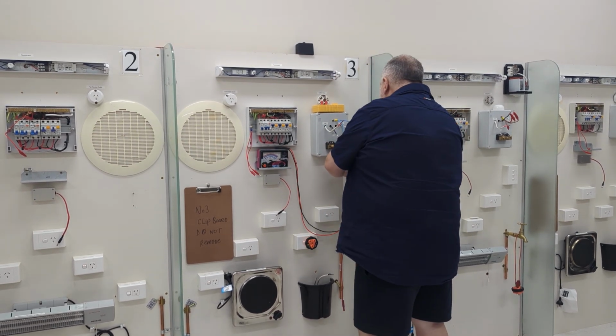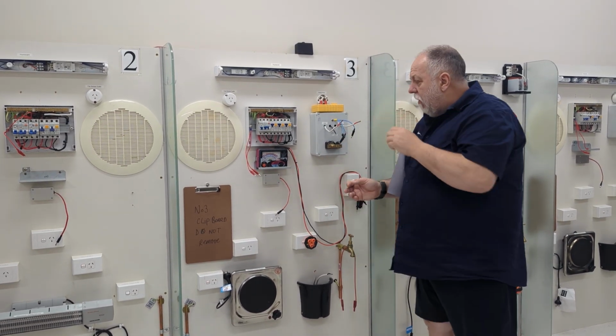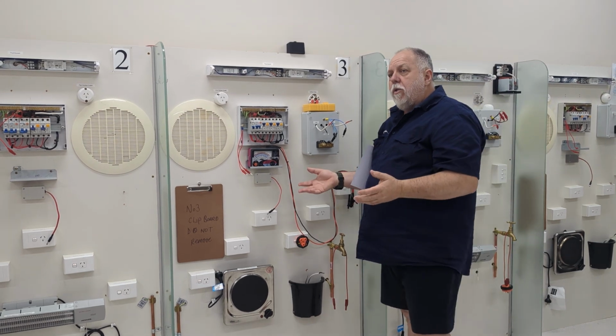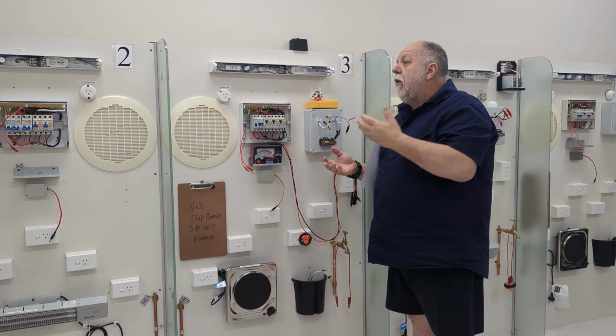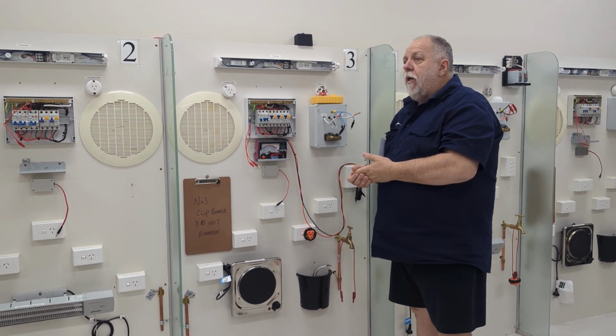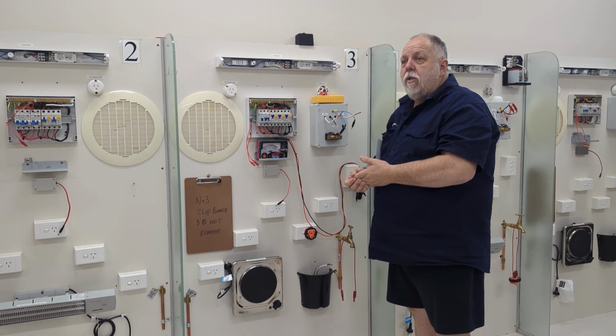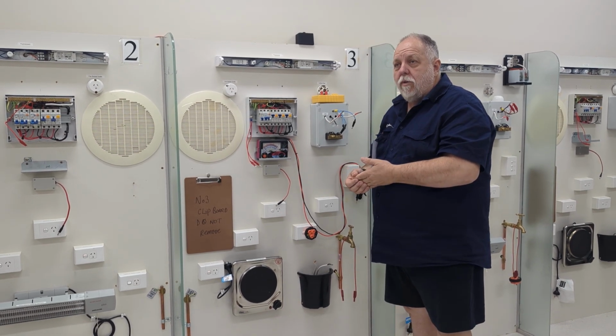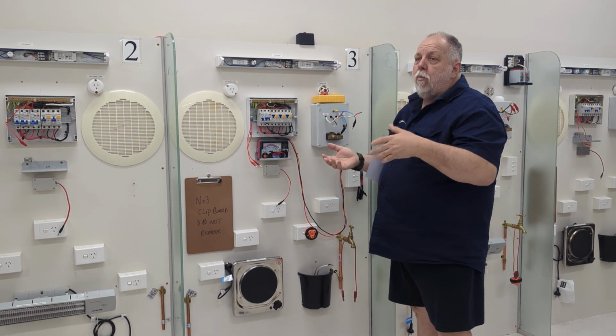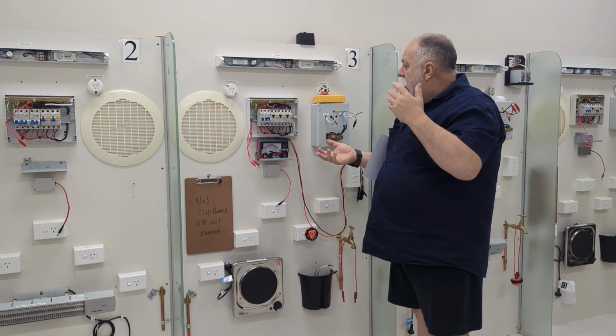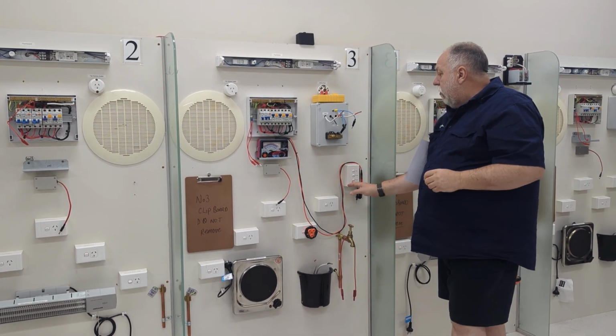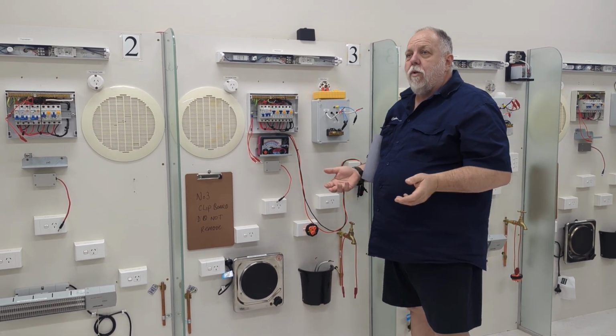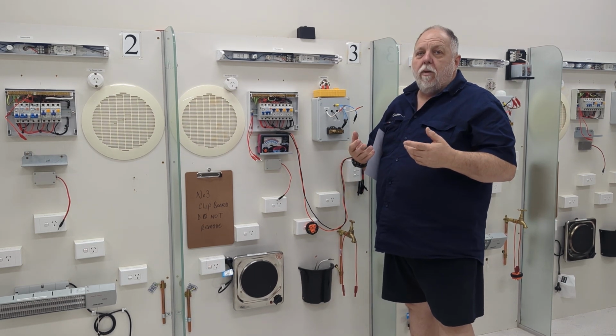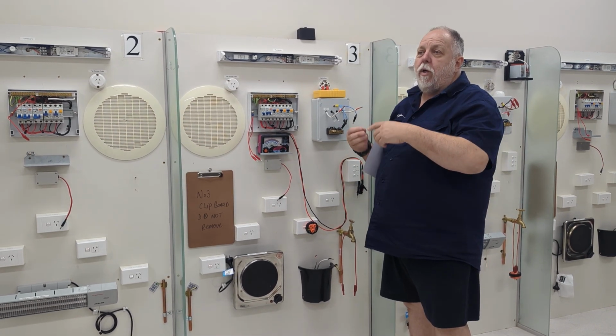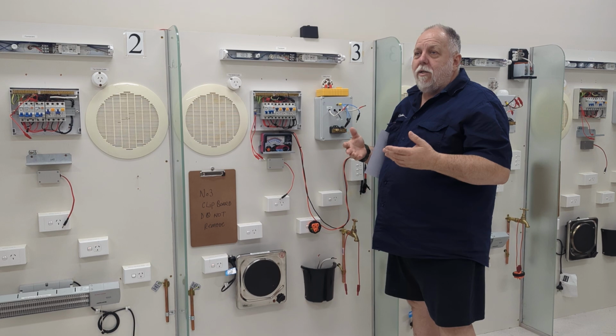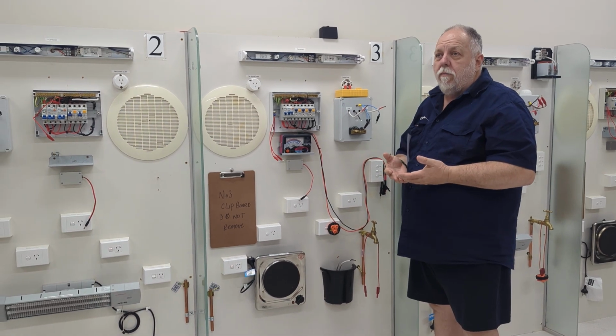All right. So, as I said, you remove all your appliances. Make sure that there are no electronic dimmers as well, because you're going to pump 500 volts in there for an insulation test. The dimmer might not like it. Does that make sense? So you remove that or bridge them out, whatever they want to say. Make sure all your switches are on too when you're doing the whole installation. That's something I talked about yesterday, because you will need to test if you've got twin active down the wall or anything. We need to be testing all of the wiring in the installation.